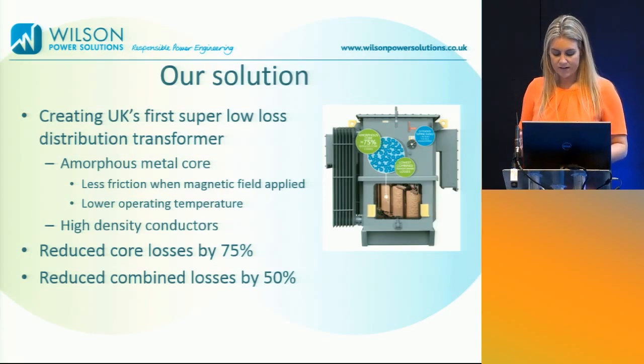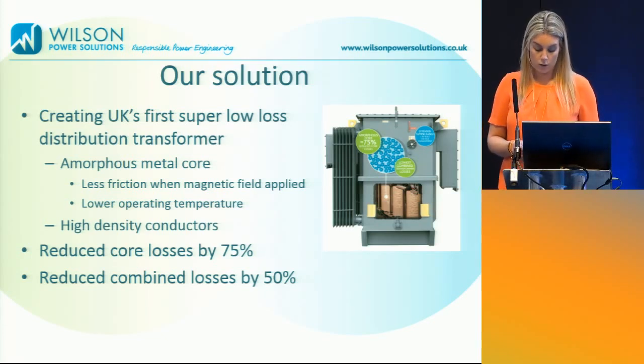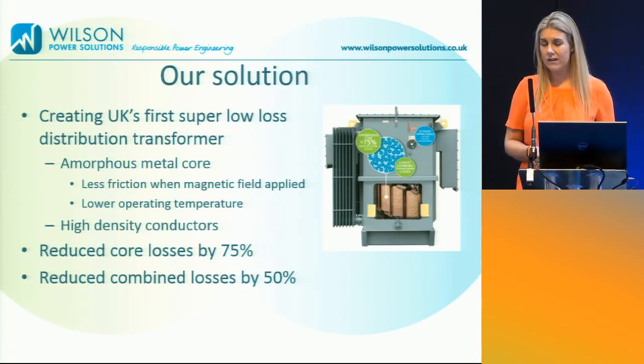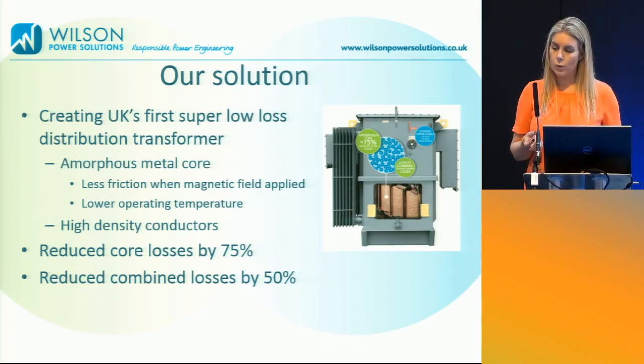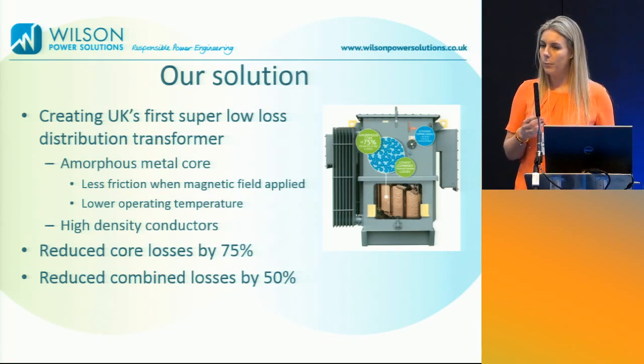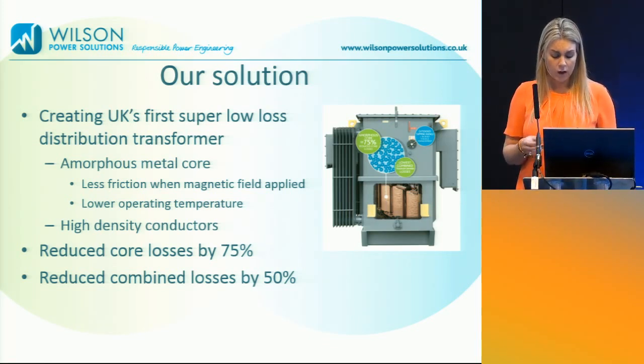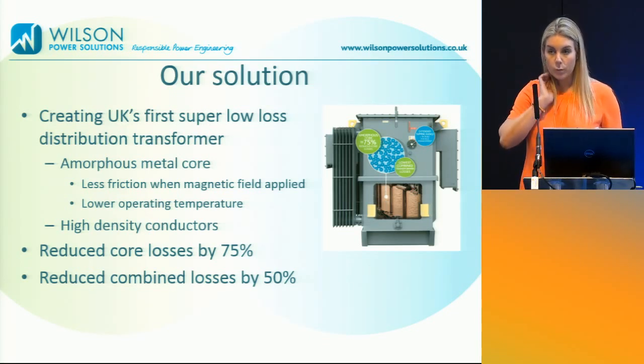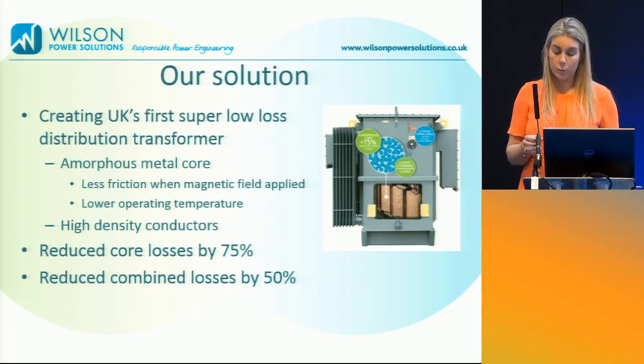So we as a business set out to create the UK's first super low loss transformer. The concept was easy - there are two types of energy losses when a medium voltage distribution transformer is live: copper losses and core losses. Copper losses, sometimes referred to as load losses, depend upon the varying load of your transformer. Core losses are fixed, present from the moment the transformer is energised, effectively 7 days a week, 365 days a year. There have been efforts to improve the energy efficiency of transformers over the years in Western Europe and the US.